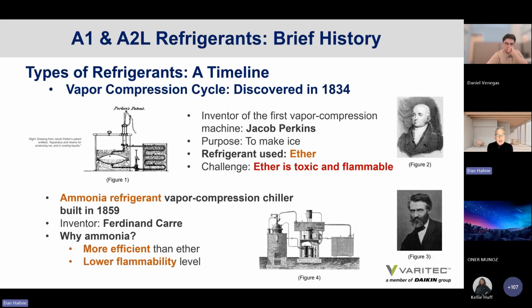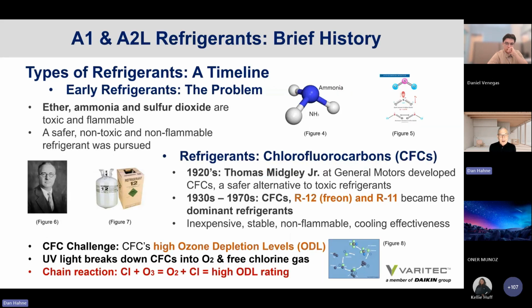In 1859, Ferdinand Carre came up with an ammonia refrigerant vapor compression chiller. Why ammonia? Because it was more efficient than ether, and it had a lower flammability level as well. Well, obviously, there's a reason why that was considerably popular at the time. However, ether, ammonia, and sulfur dioxide are toxic and flammable, and there was a significant pursuit of a safer refrigerant, and that refrigerant was discovered or invented by Thomas Midgley of General Motors back in the 1920s. And he used a CFC refrigerant, a chlorofluorocarbon refrigerant. And it became the dominant refrigerant of choice for HVAC systems from the 1930s through the 1970s.